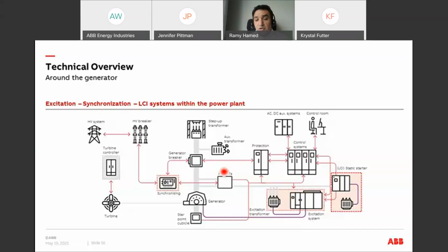Next, we move to where the excitation system is in the plant. So as we explained, here we have the generator, and this is the turbine, and this is the turbine governor to control the operation of the turbine. And similarly, for the generator, the excitation system is connected to the rotor to generate and regulate the voltage. And the excitation system is supplied from the excitation transformer, which, as we explained, is in most cases fed from the generator terminal.